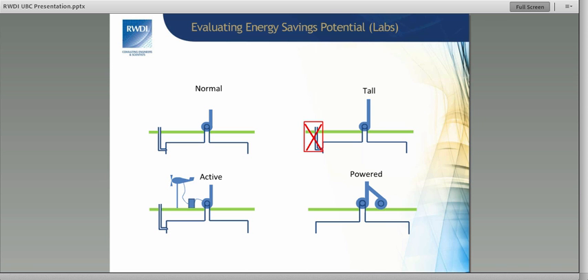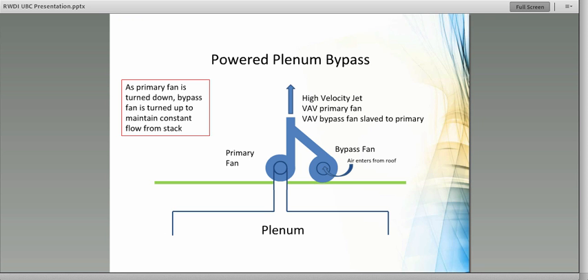Another way you can do this is called powered bypass. So instead of just bringing extra air into a real big fan, what you do is you have two smaller fans. One that runs in normal mode. And when the demand from the building decreases, what you do is you have this bypass fan, often called a slave fan. And it can be small. And what it starts to do is it starts to power up, and it provides air into that stack while you're reducing the demand from the building. So you're still maintaining that air from the top of your flue. You're maintaining your momentum. You're maintaining the airflow from that flue. You're maintaining the plume rise from that flue. So there's a variety of ways you can do this, but the whole idea is to be able to save energy safely during times that we don't need so much demand from the building.